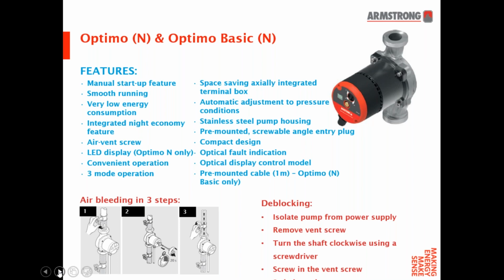Space saving axially integrated terminal block, automatic adjustment to pressure conditions, and with it being for potable water, as we said before, stainless steel pump housing, pre-mounted screwable angle entry plug for the electrical connection, and in the Optimo N Basic, this again is pre-wired with a 1 meter long cable. Compact design, optical fault indicator, and an optical display control model. Air bleeding is exactly the same, so I won't go into that, and also de-blocking is in exactly the same manner as the Optimo range from the heating side.